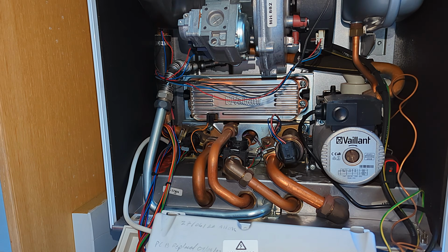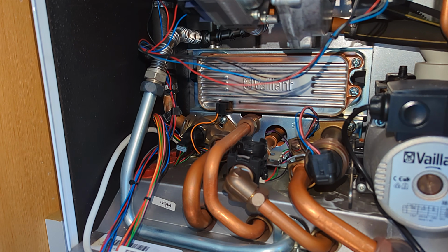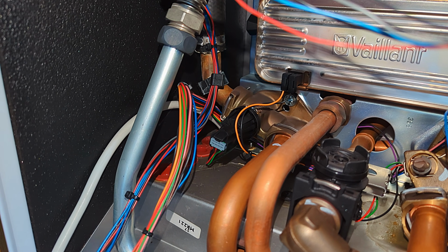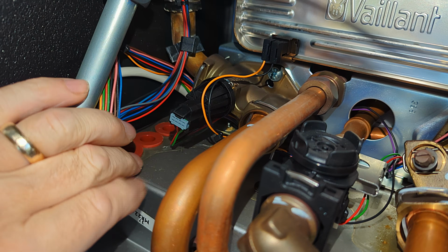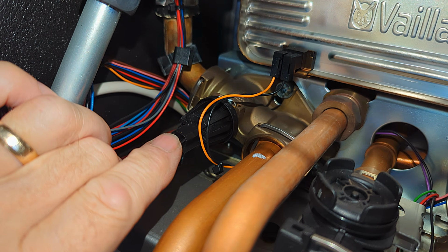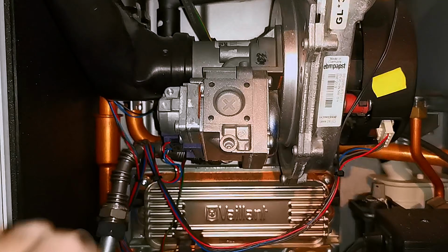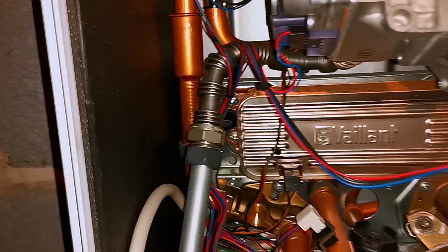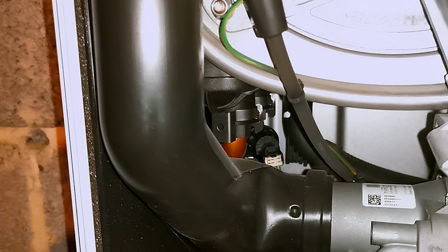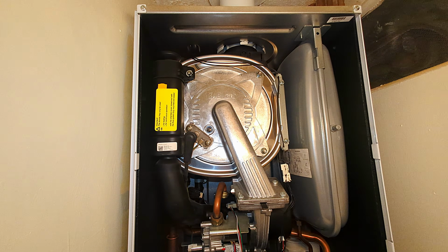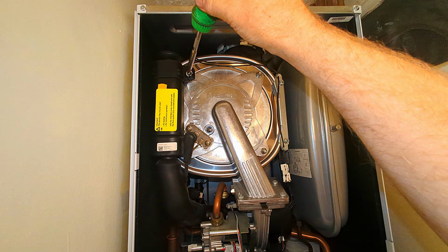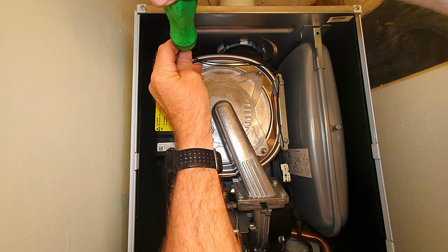Now, depending on the age of your boiler, it depends on where your pressure sensor is going to be. On your older boilers, the pressure sensor is down at the bottom here, and that's the pressure sensor just there. On the newer boilers, the pressure sensor is in the middle of the boiler and it's on the return pipe. I need to remove the air inlet tube to get to this pressure sensor. It's just one screw, it folds down and then just pulls away.